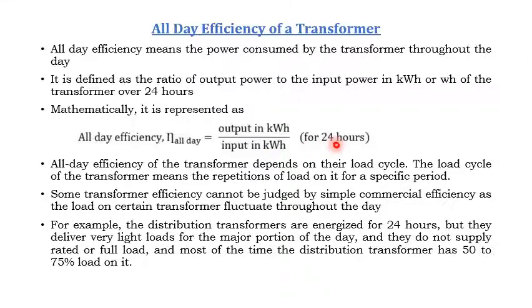Here the all day efficiency of a transformer depends on its load cycle. As I said, the load is continuously changing. The load cycle of a transformer means the repetition of load on it for a specific period. For example, a transformer is having a load of 500 kilowatt. This load may drop to 100 kilowatt, or it may go to 200 kilowatt or 400 kilowatt, whatever it may be.